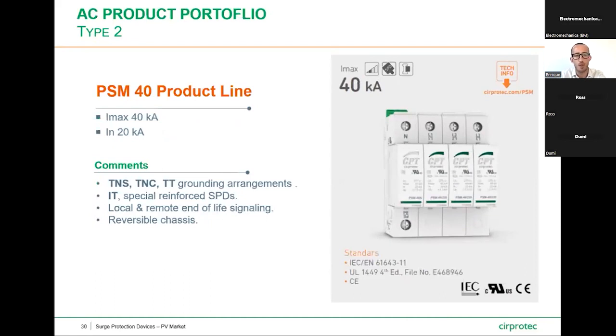Then we have the type 2 product range. It's named PSM 40 with an Imax of 40 kA and an In of 20 kA. The same as the type 1 plus 2, it's suitable for TNS, TNC, and TT networks. We also have special reinforced SPDs for IT networks. And we have solutions available for local and remote end of life signaling according to the different requirements of our customers. The same, the cartridges are reversible to assure a better suited installation process.